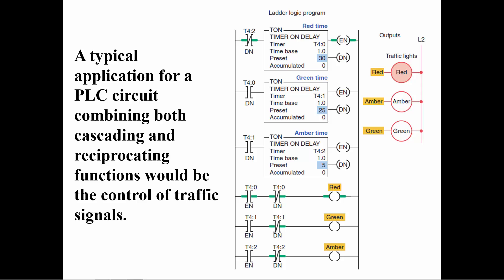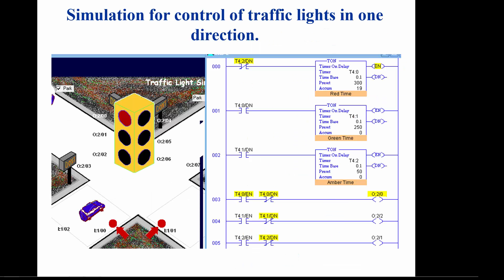The last three rungs actually turn on the lights. Each light is turned on when its respective timer's enable bit is true and its done bit is false. The simulation has been captured about two seconds into the timing for the red light. Observe how the done bit of each timer controls the next timer in sequence.